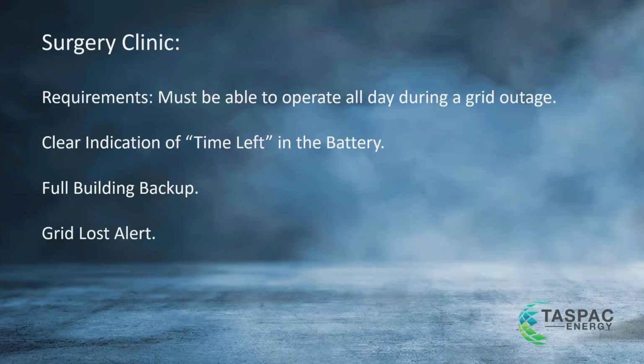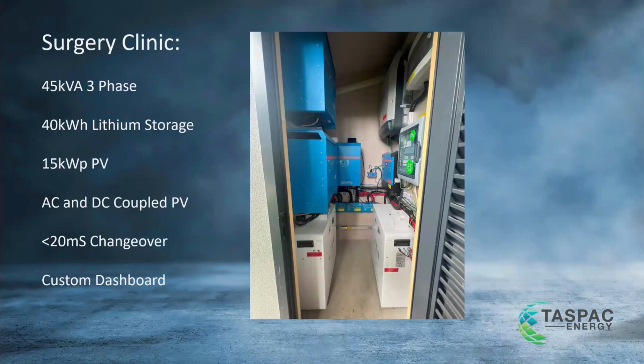We want full building backup, but they also wanted to automate the aircon to turn off below a certain battery level. And they wanted an alert if the grid goes down, because with really fast changeover they don't actually notice - the lights don't even flicker, so they could be pottering away with the aircon still running full noise and not even know. So they wanted an alert, which turned out being a flashing light in a hallway and a buzzer with a mute button - the buzzer just goes when the grid goes down. Easy, all that can be done with the Victron system.